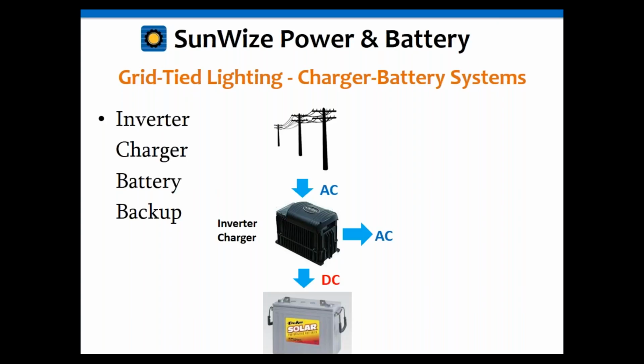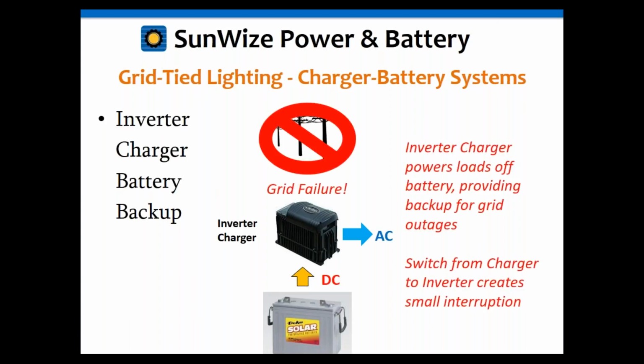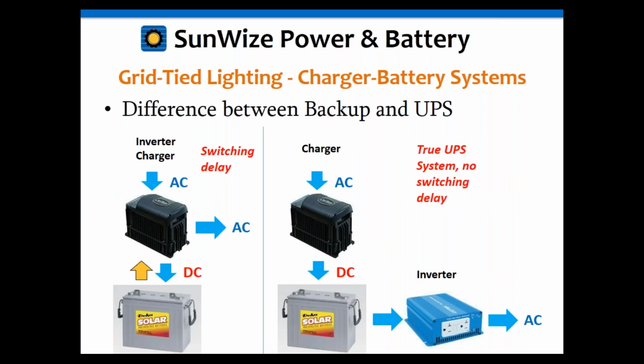Obviously, if you have other type of lighting controls that may not be an issue. Hey, it can be down for 5-10 seconds, nobody cares. But just keep in mind that there can be a switching delay that may be a problem with those applications. So in a true UPS, what will happen is that you basically have a straight up charger. So the charger charges the battery, and then the battery then powers up the inverter. So you literally have two separate components. You have a separate battery charger and a separate inverter. What this means then is since the inverter is always running off the battery, it doesn't really matter what happens on the AC side. That inverter is always powering up that load, and there is no switch delay.